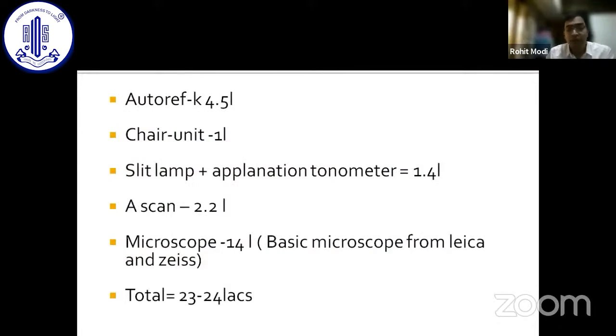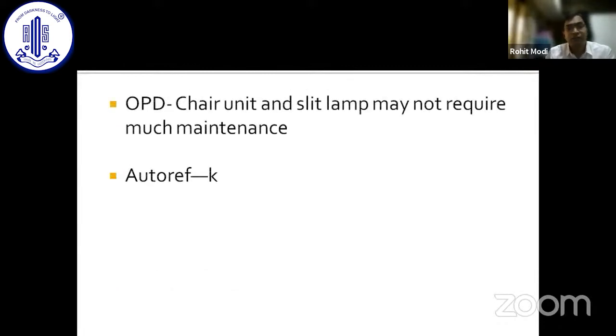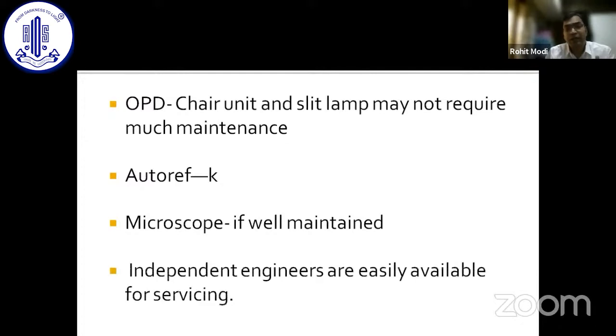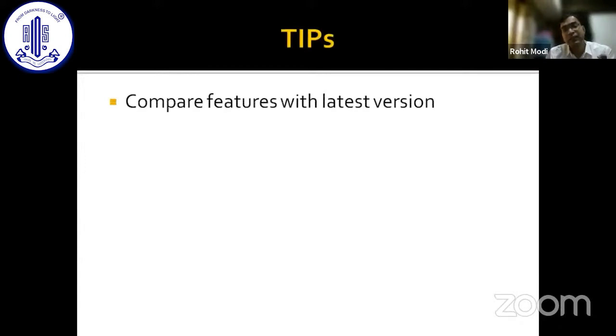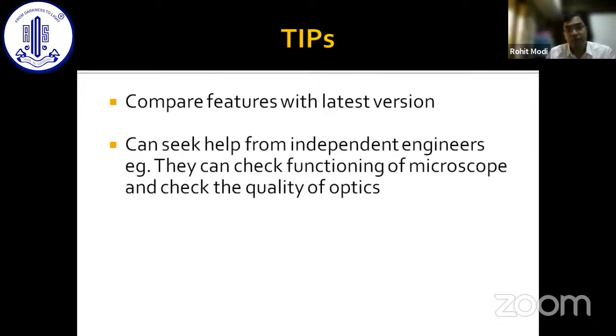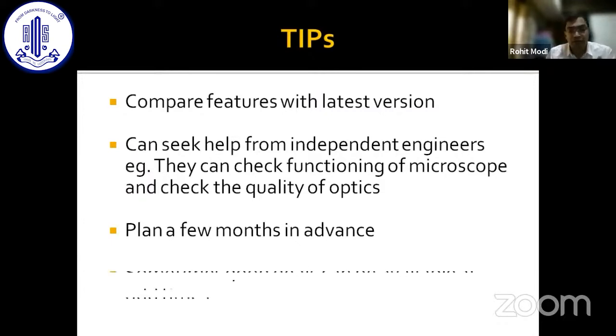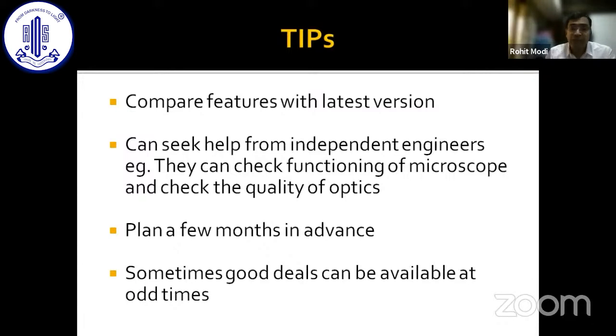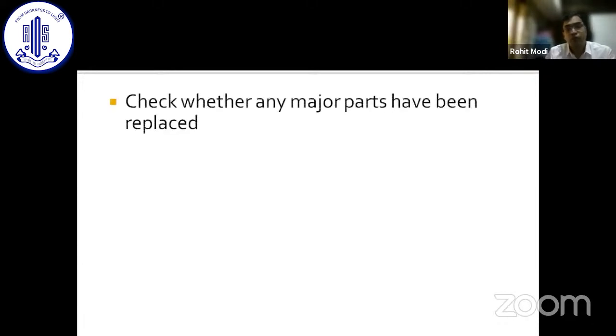Now, which are the equipments you can think of easily getting refurbished? I believe the OPD setup and the microscope, because these equipments require the least amount of care. The total equipment cost for OPD plus the microscope, if you buy new, could be 23 to 24 lakhs, which can be cut down by at least 40 to 50%. The OPD chair and slit lamp again wouldn't require much maintenance. Auto ref K run for years well, and so does a well maintained microscope. And independent service engineers are easily available in the metros, who can assess the status of the refurbished equipment.